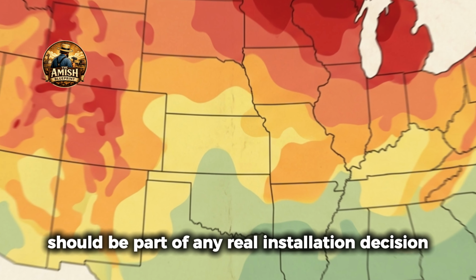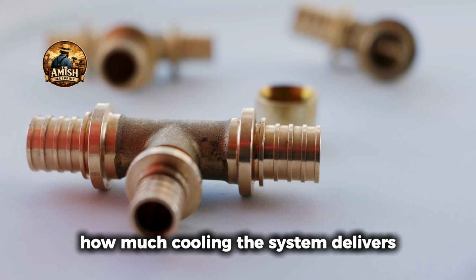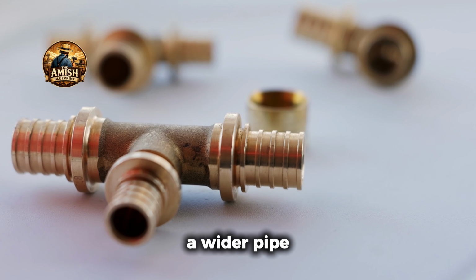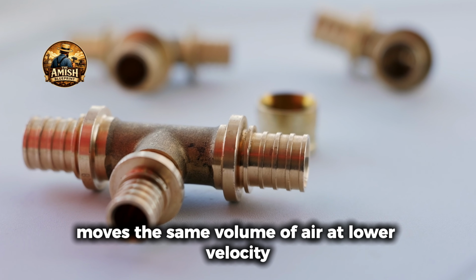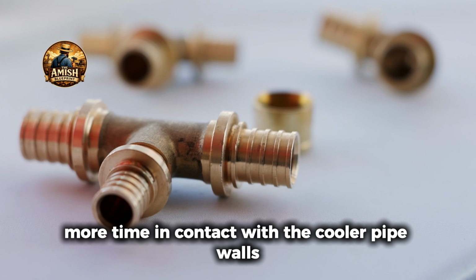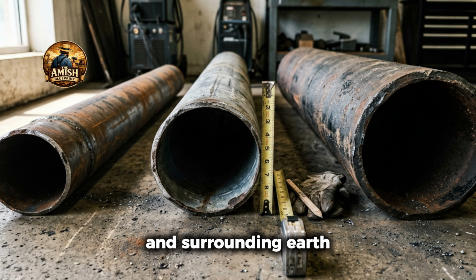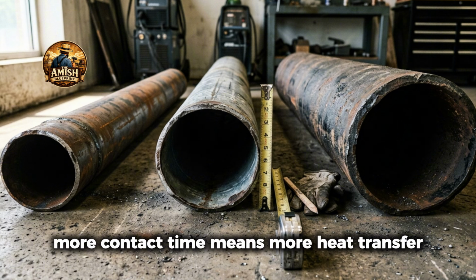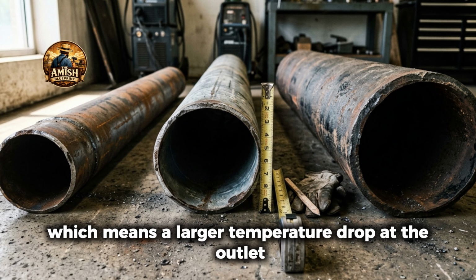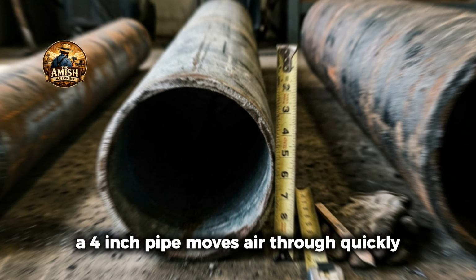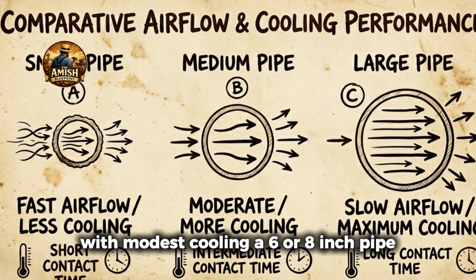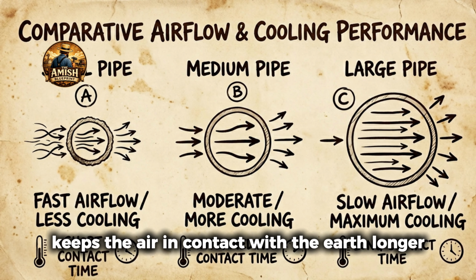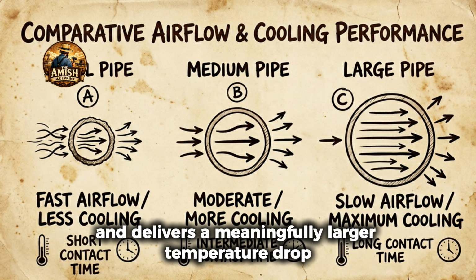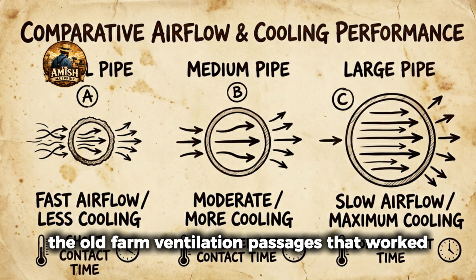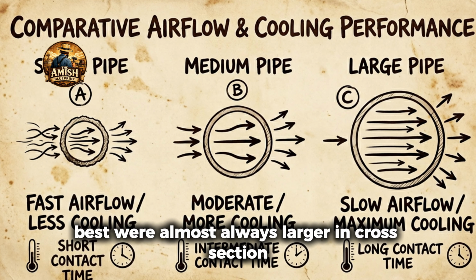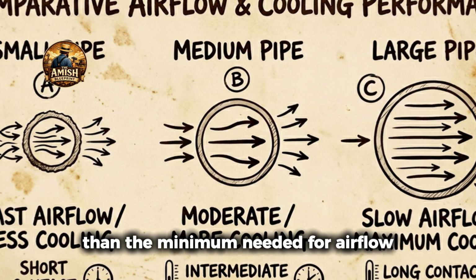Pipe diameter is the variable that most affects how much cooling the system delivers. A wider pipe moves the same volume of air at lower velocity. Lower velocity means the air spends more time in contact with the cooler pipe walls and surrounding earth. More contact time means more heat transfer, which means a larger temperature drop at the outlet. A 4-inch pipe moves air through quickly with modest cooling. A 6 or 8-inch pipe at the same airflow rate keeps the air in contact with the earth longer and delivers a meaningfully larger temperature drop. The old farm ventilation passages that worked best were almost always larger in cross-section than the minimum needed for airflow.